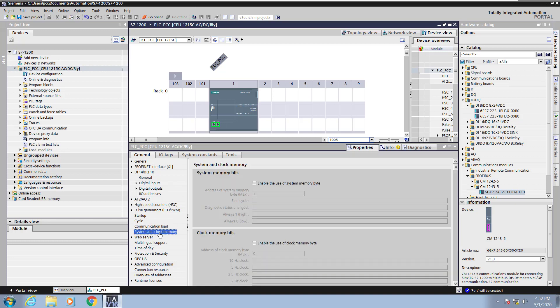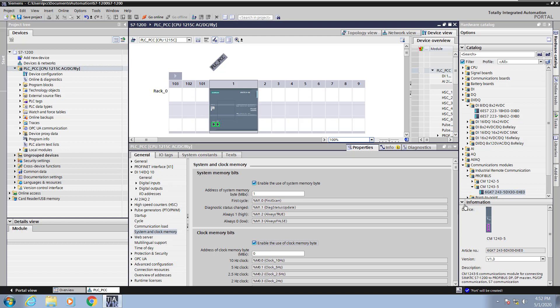Next I will select the system and clock memory area. I can enable one byte for the system memory bits that have predefined tasks. I can also enable the clock memory bits as well. Each bit in the clock byte cycles at a different frequency on and off.